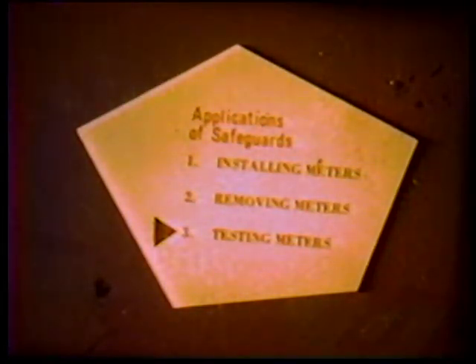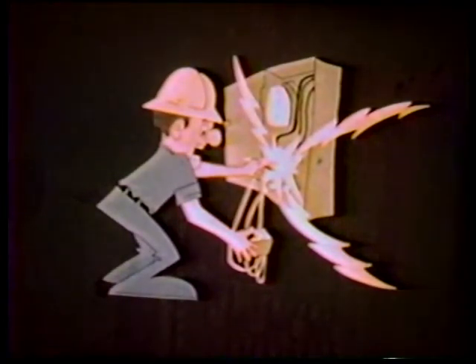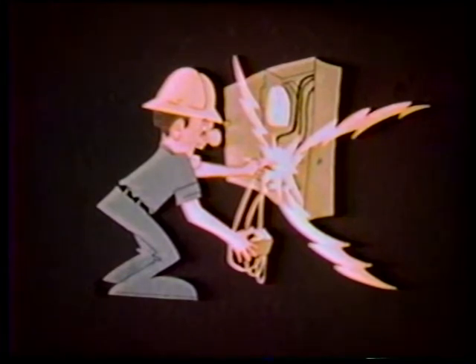Finally, let's talk about safety in testing or repairing meters in the field. Accident records show that many electric flashes occur when metermen are testing or repairing meters in the field. Use of the proper insulated tool can be very helpful in preventing this kind of accident. Perhaps flashes occur frequently during testing because the meterman gets so involved in testing he forgets about the hazards of the job. Care and planning is required for tests to be conducted safely.